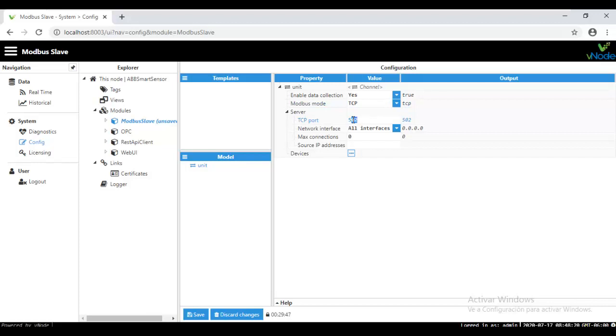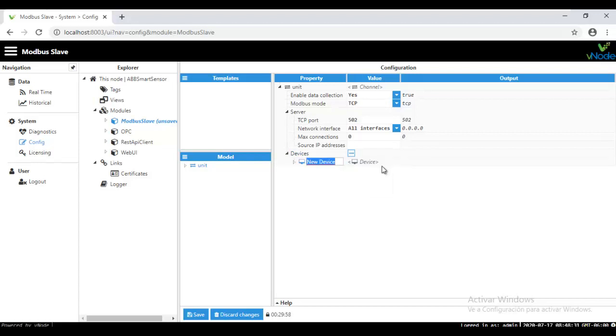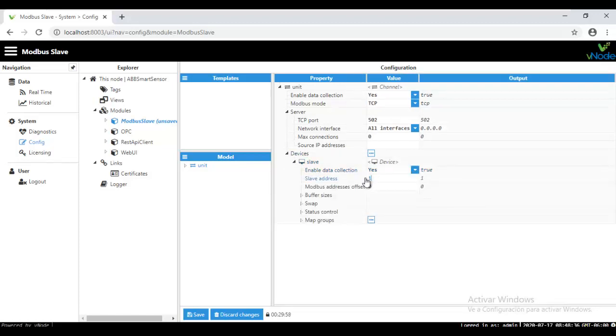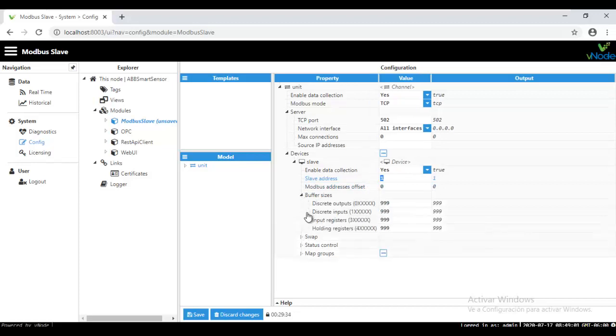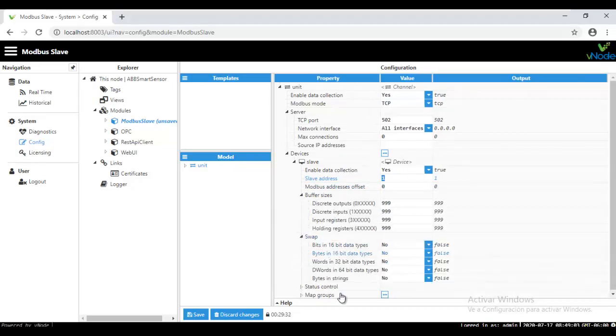And then under devices, you are going to create the slave environment, the slave device. So in this case, I'm going to put it like slave. And under the slave address, I'm going to select one slave address of my choice. Remember that you are creating a Modbus Slave device right here, so you have the full freedom to start configuring as you want. So I'm going to put it like a slave address on one. And then we have to configure any kind of offset for the Modbus address, buffer size, the swap from the bytes or bits.